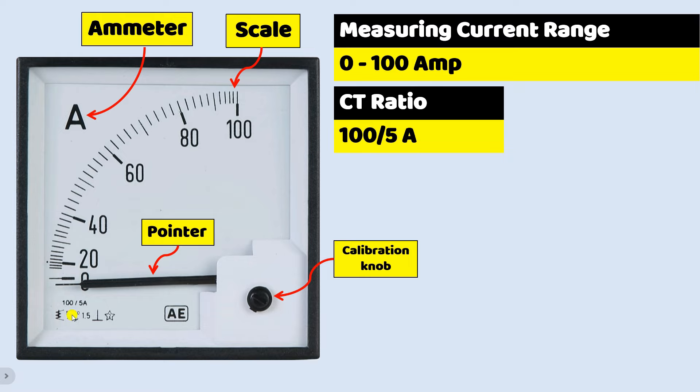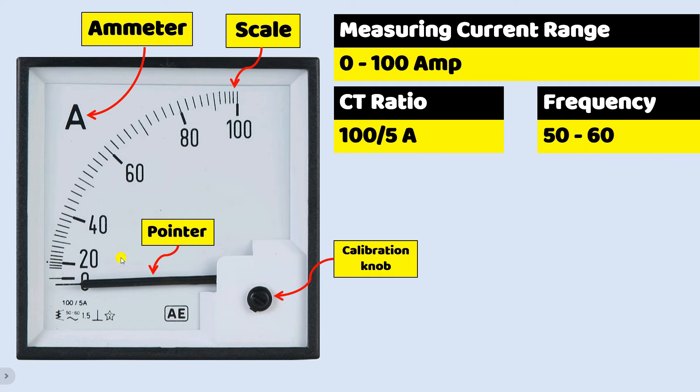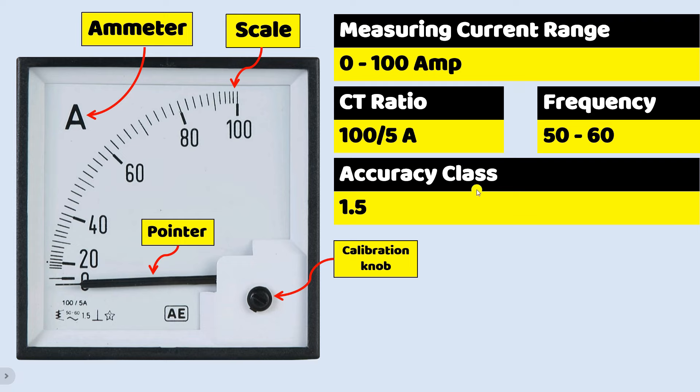Apart from this, it is written here 50 by 60. It means frequency. At how much frequency this ammeter will be used, this detail can be seen here. At the side of this it is written here 1.5. 1.5 means accuracy class, or you can call it error ratio. At the time of measuring current, the percentage of error that can occur through this ammeter is shown here.